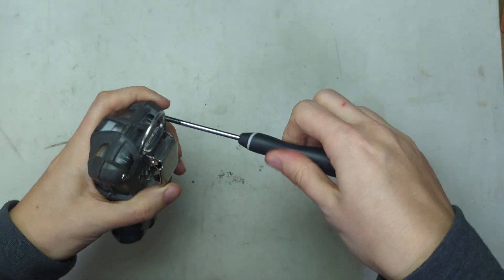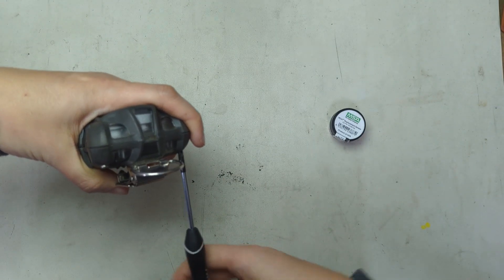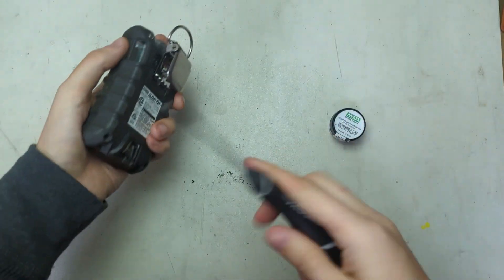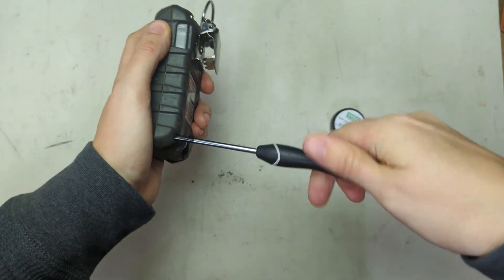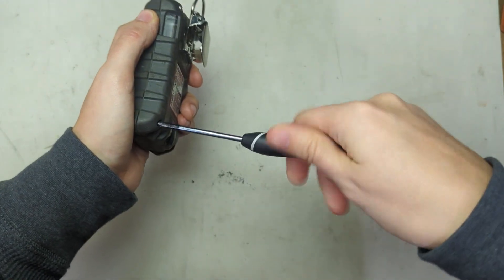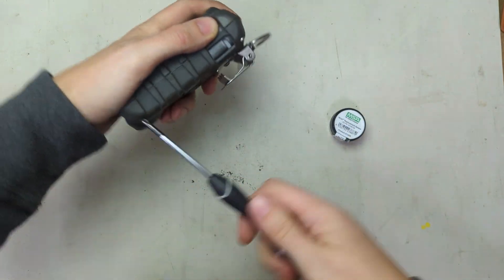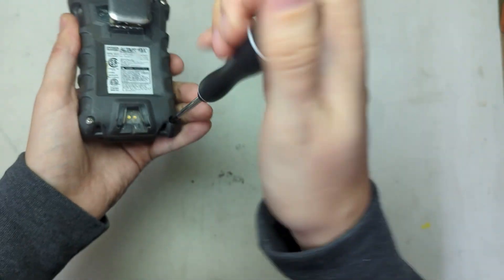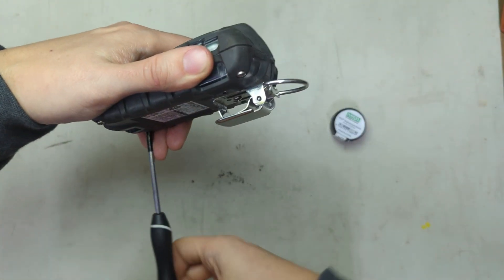There's one special function to remember about the oxygen sensor, and I'll remind you at the end as well, but once you install it, I need you to wait for about 45 minutes to an hour before you go and try to zero and calibrate it. Any time you replace a sensor on one of these units, you want to make sure that you do a zero and calibration afterwards. I've got videos on that as well, you can probably find them at our channel.